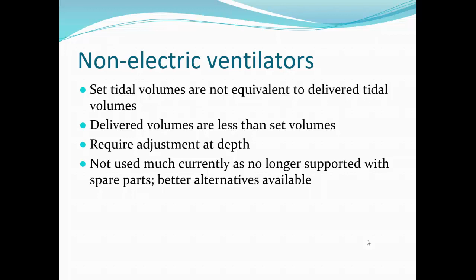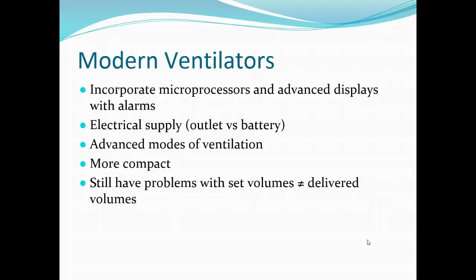The modern ventilators incorporate microprocessors, advanced displays, and alarms. I mean, you see it upstairs all the time. Typically, you can do battery-operated for the ventilator. Some chambers will allow for a feed-through, so you can pass the electrical supply out to outside the environment. You can typically do advanced modes of ventilation. They're more compact. But again, a lot of these modern ventilators still have problems with tidal volume and giving the volume that you want at a different pressure.